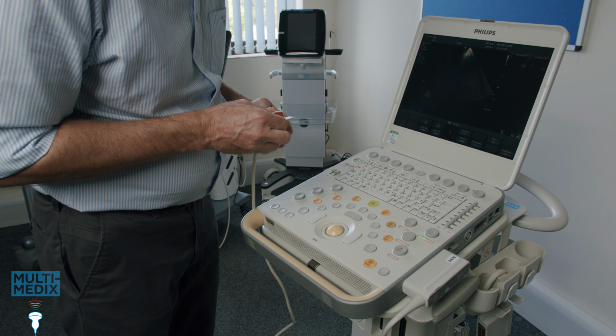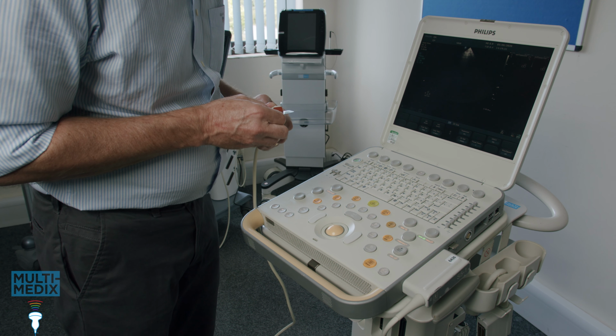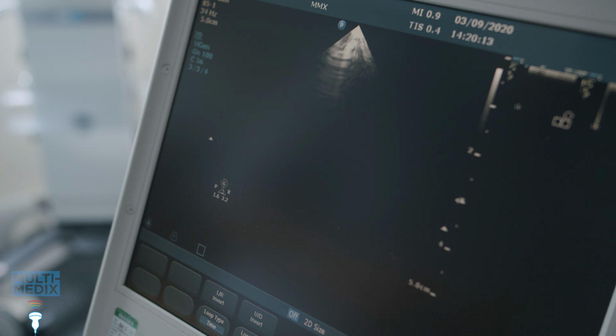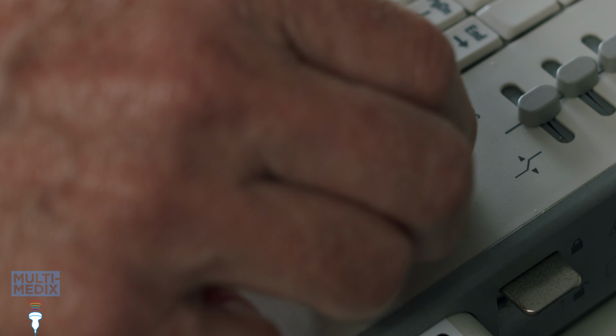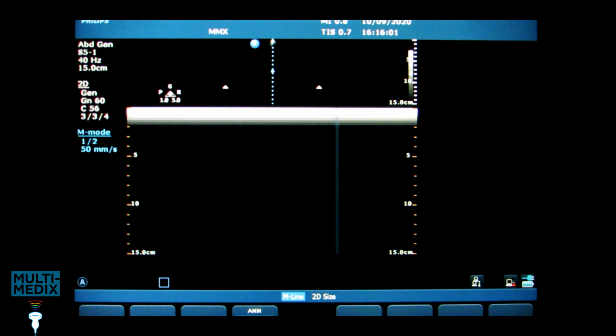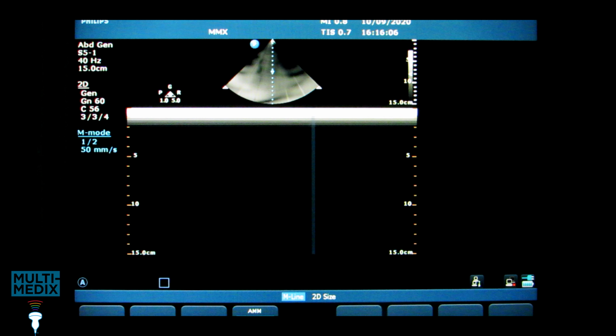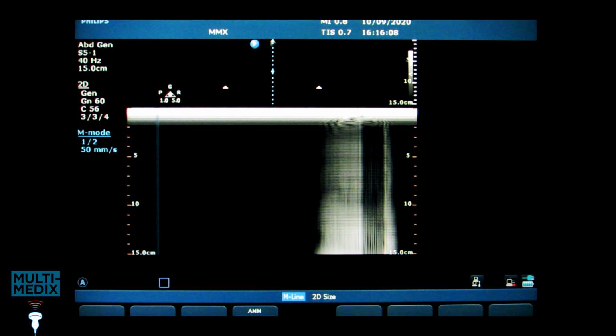The ultrasound reverberates in the tool, giving a comet tail appearance, which dims or disappears as it crosses a dead element. Make sure that the depth and focus are set deep enough for the whole array to be active. You can check this by touching the paperclip near the end of the array. If you don't get a signal, increase the depth and focus until you do. The best way to do the test is with a smooth sweep along the probe, then freezing the image to see the trace. I find I have to do a few sweeps until I'm confident about whether there's dropout or not. Changing direction helps as well.